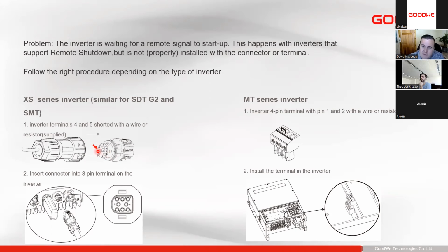So all these plugs you'll see have a remote disconnection terminal. That is a safety feature that is used in some countries. So if it is used in your country but not necessarily on all installations, when you select your country code, it will enable this feature. If that plug is not plugged in, the inverter will not operate. It will remain in a waiting mode. So we always need to make sure that it is correctly inserted.